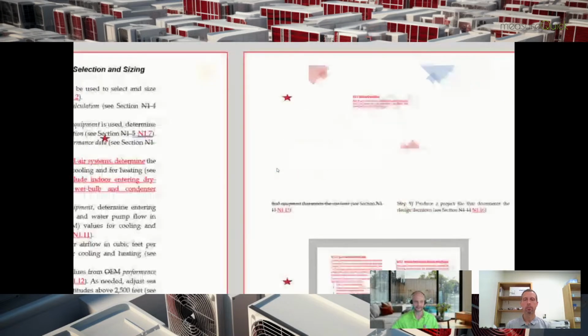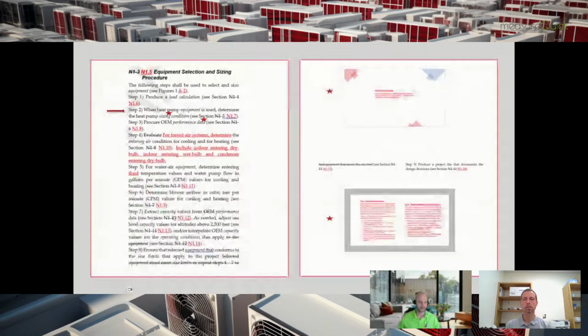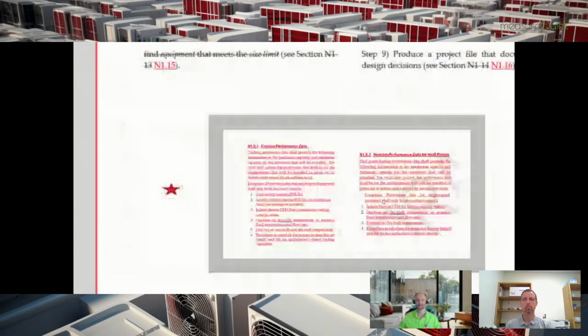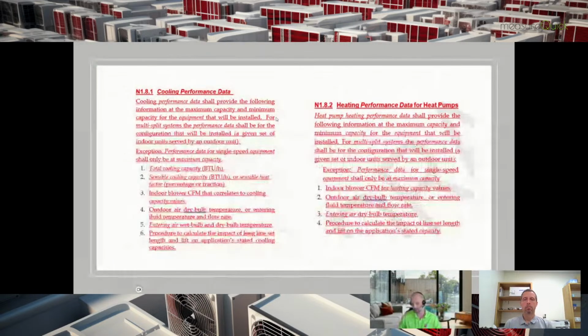And then if we get down here, it talks about the OEM expanded data. That's what we used to call it in the original Manual S. Now we're just calling it performance data. We need the performance data from the manufacturers to be able to size this stuff correctly. And here's the minimum requirements that we need. We didn't used to need all of this stuff, because it wasn't a thing. Before we got into inverter heat pumps and multi-stage heat pumps and two-stage heat pumps and air conditioners, we didn't have minimum capacity and maximum capacity to look at. We just had one single capacity to look at. So this states minimum and maximum capacity for the equipment that will be installed.